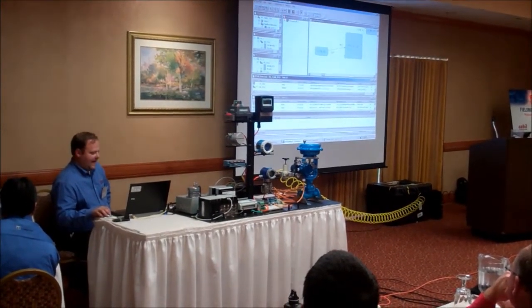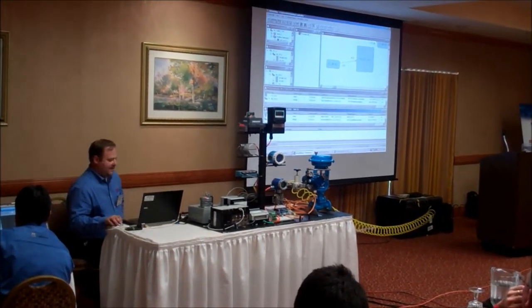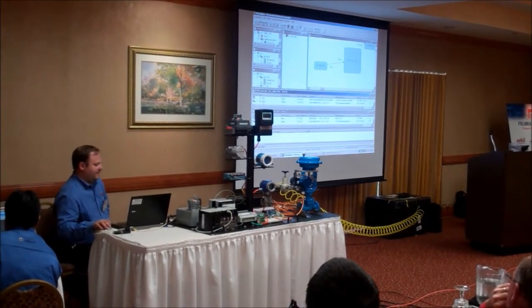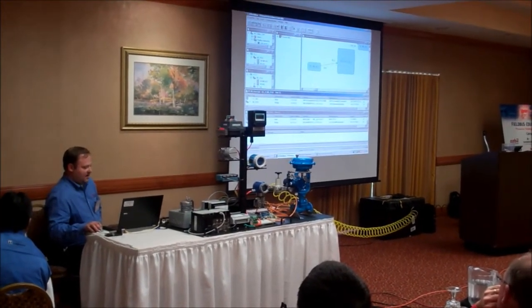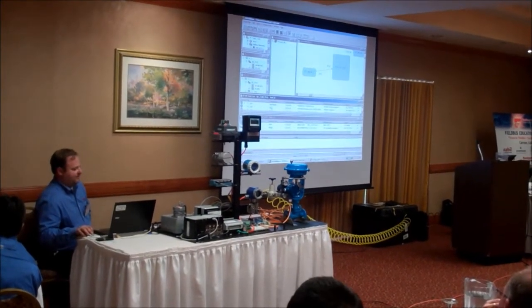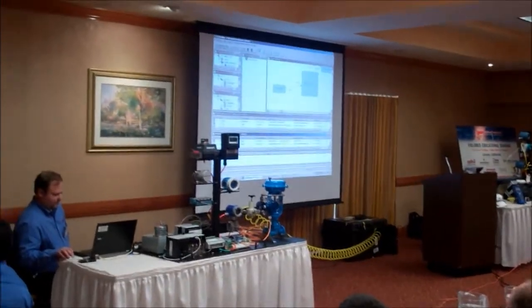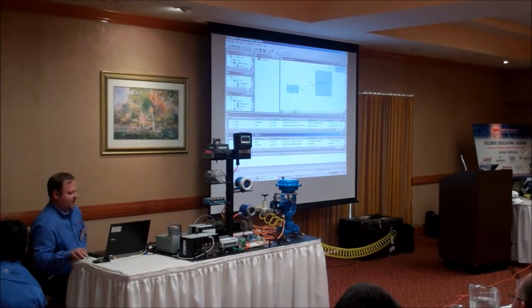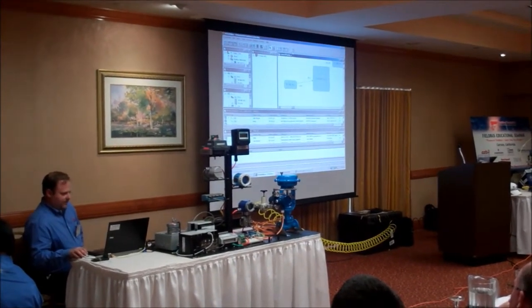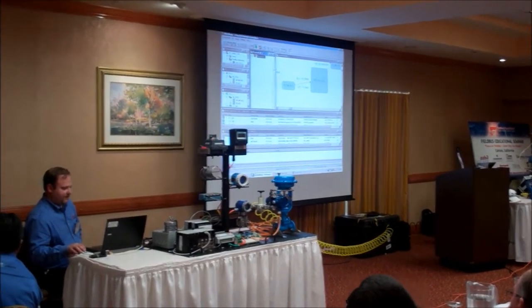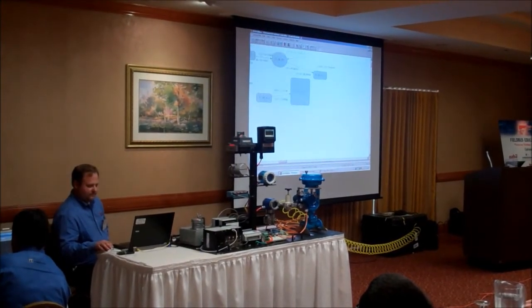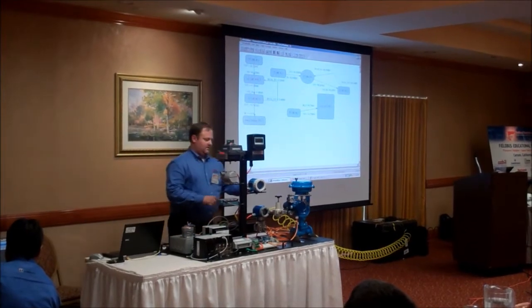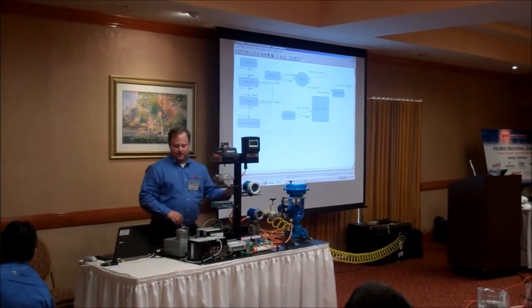Basically, as John was talking earlier, you have two link active schedulers and backup type devices. In this case, we use the FFLD as the bridge and also the master on the link. The backup is the TT200 — it's the backup link master. Additionally, the FFLD is the master on the other link, and in this case the TC100 — the SMAR — is the backup link master. So I set up this control valve scenario, and we're going to enlarge this. We have two situations: this one controlling off the temperature transmitter, and this one controlling off the Rosemount.